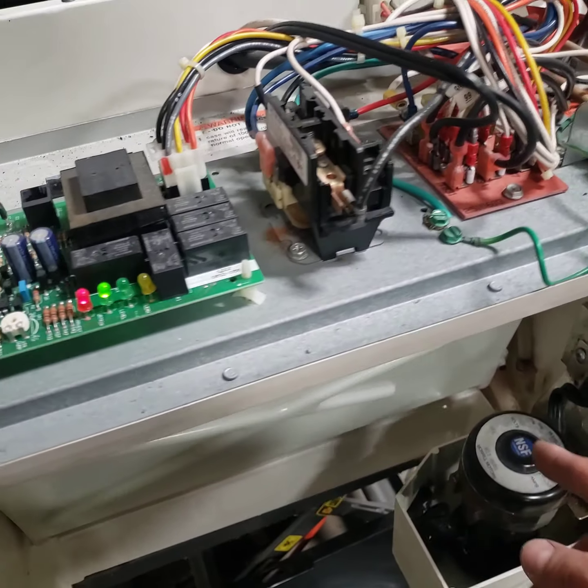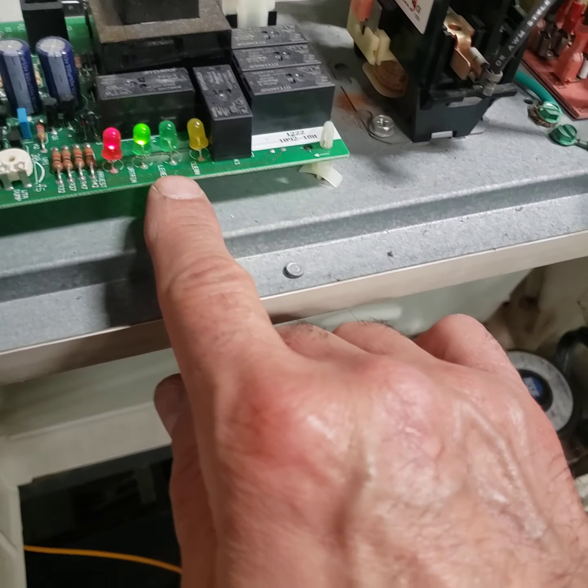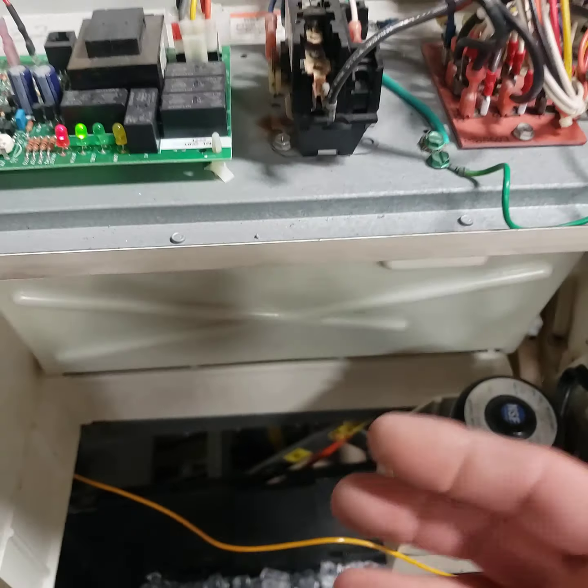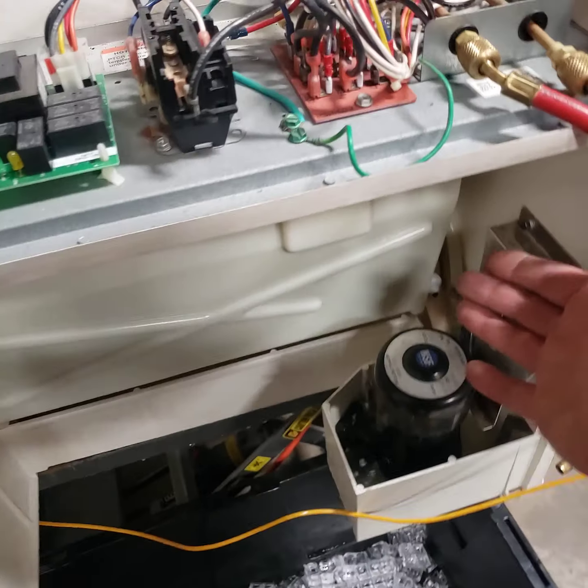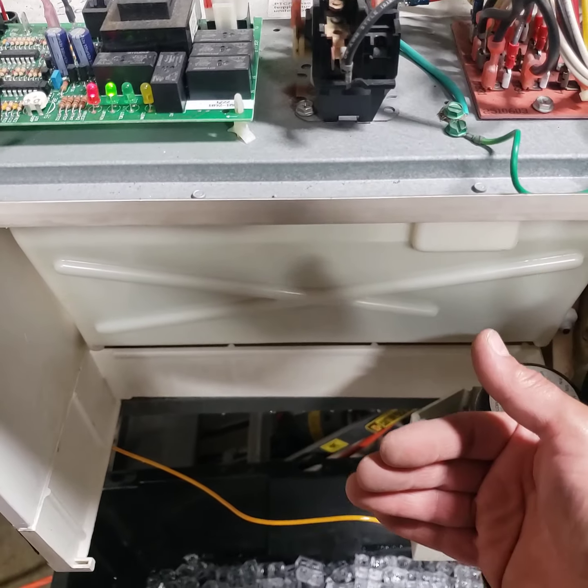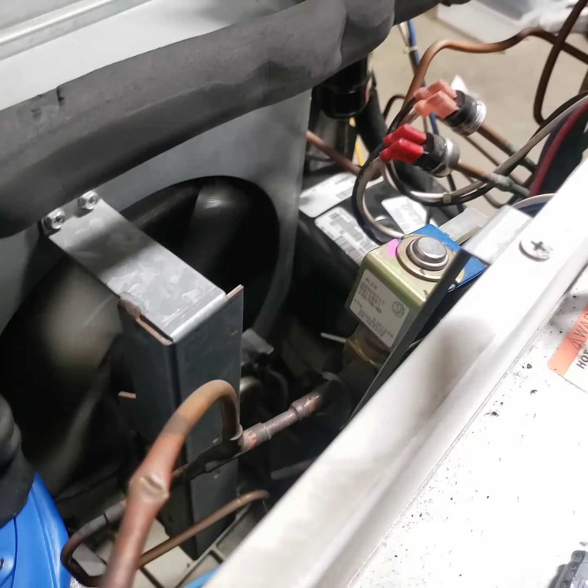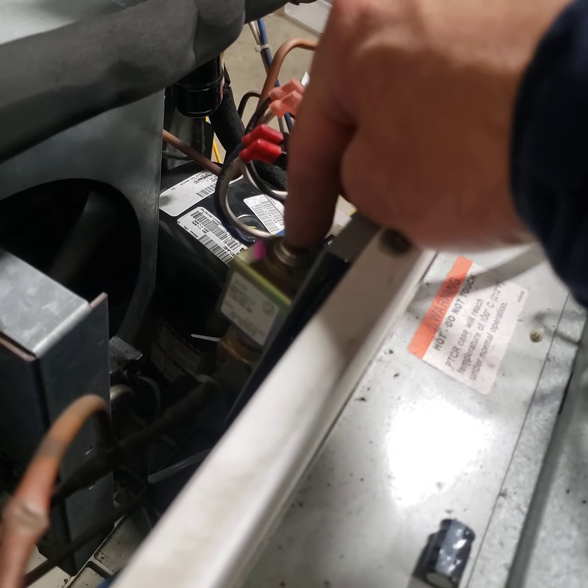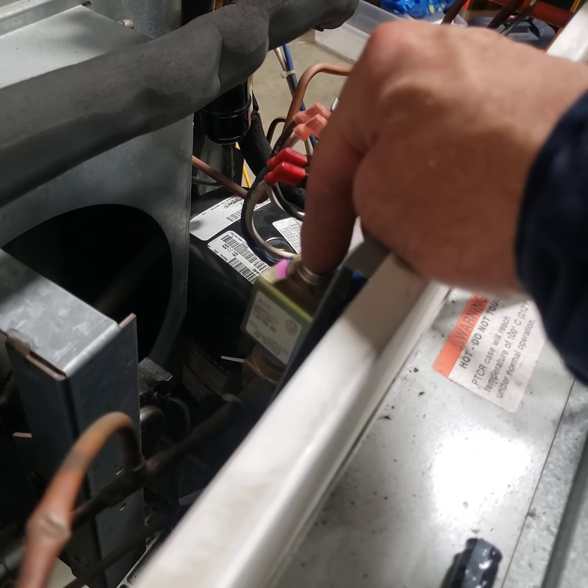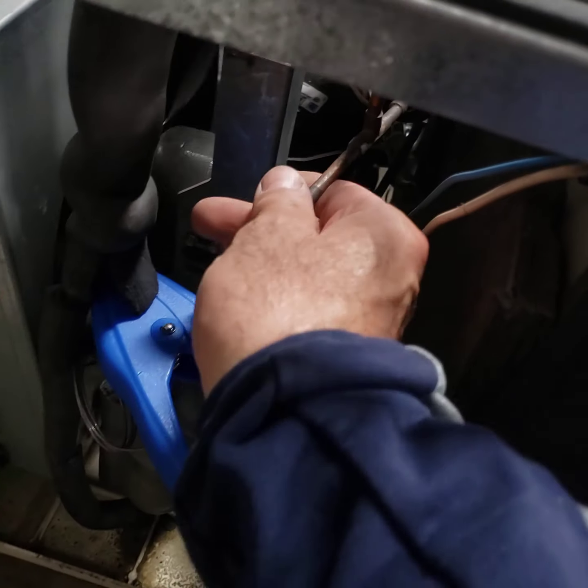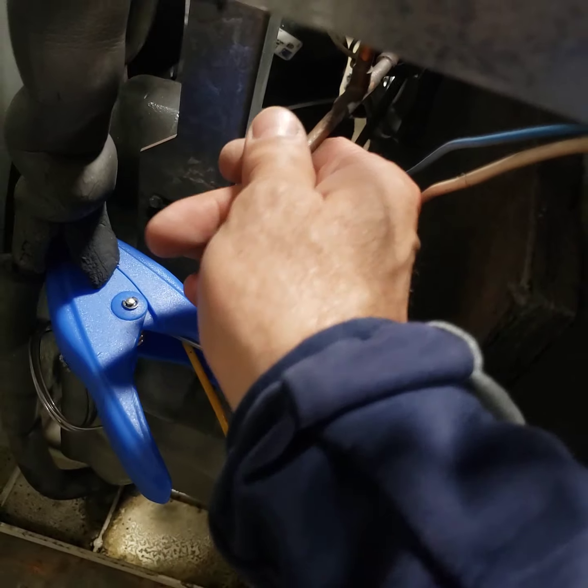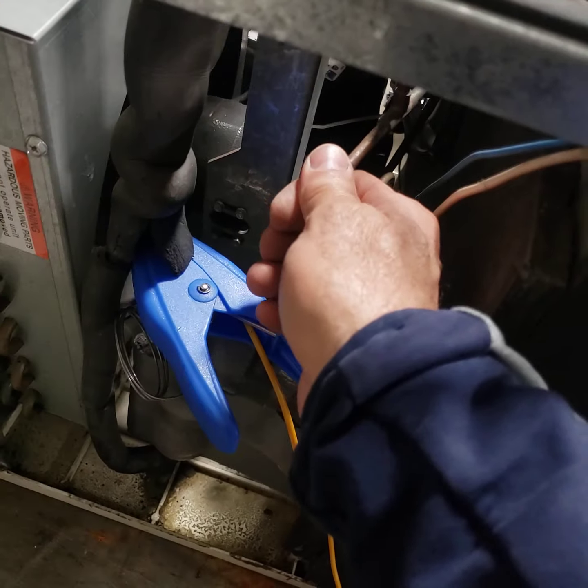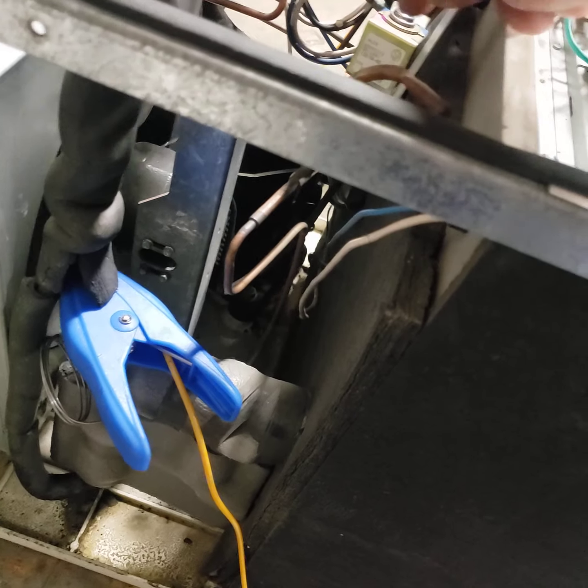The only time the curtain light turns off and on is for a second when the ice is harvested. See, the condenser fan stopped, as I told you it would. The hot gas bypass is open. If I put my hand here, I can feel it's hot, so that means it's working. If that opens and the harvest is coming but this isn't really hot, there's something stuck in there, it's broken.